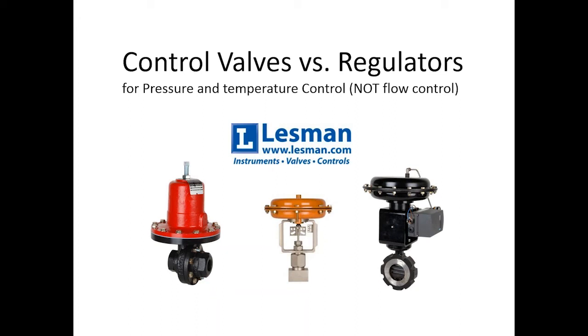The first thing you've got to remember in regulators, control valves versus regulators: regulators can control pressure or temperature. They cannot control flow.